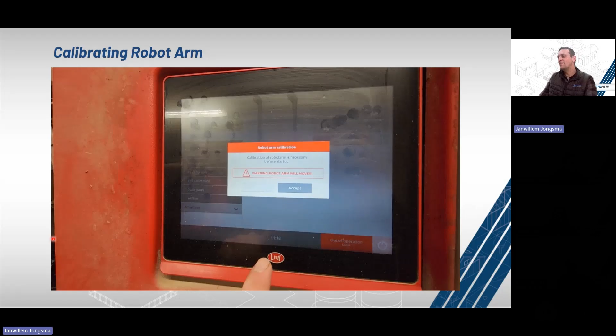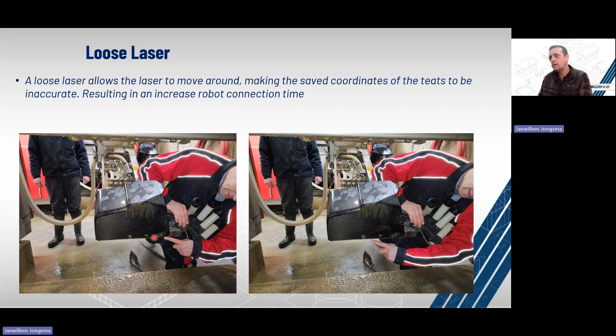Next is loose laser cover. This will affect the cup offsets. We need a fixed distance between the laser and the cups. That's to achieve an accurate attachment. If the laser moves, we no longer know where those cups are. So you can see two bolts on the side here. They can sometimes rattle loose. So this one and that one right there.